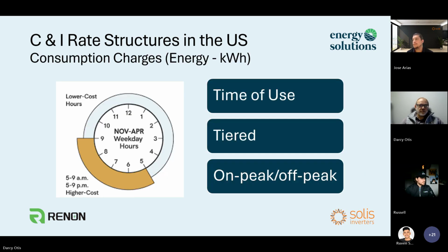The most common charge people are familiar with are consumption charges. Usually they're energy based, so kilowatt hour is the most common. They can be time of use based, so when you use that energy, and that usually depends on when the utility's costs are the highest, or when the highest demand is there. They can be a tiered structure, or a version of time of use, which is an on-peak, off-peak type of rate structure.